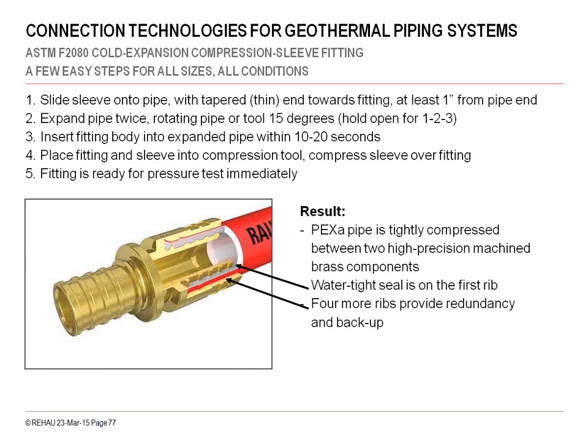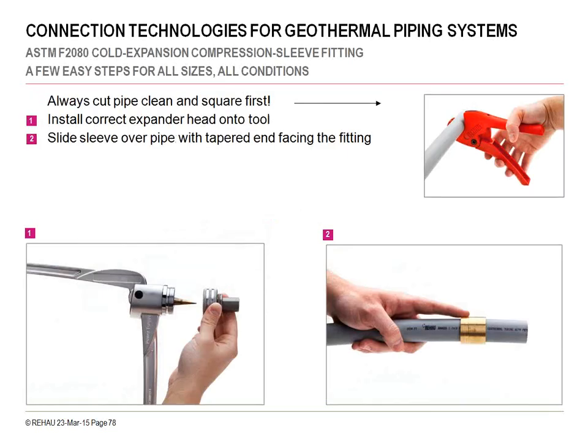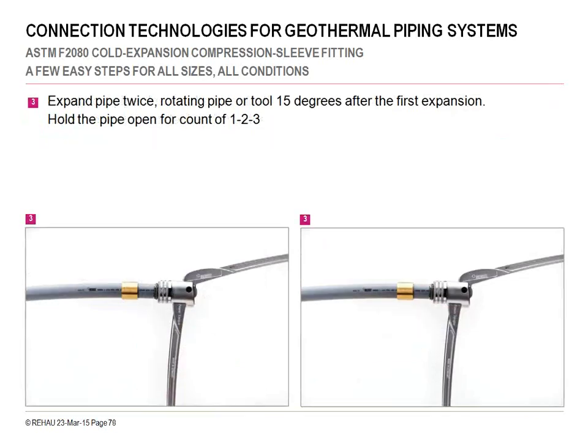If you remember the tensile strength test I was showing you, we get about 4 times the length of the piping material. We're putting about 800 pounds of force on when we're stretching that pipe out. And again, it's the pipe that gets real thin and snaps and fails, and that's what we want to see. It's not at the joint. Going through the illustration of that joining method, we want a nice clean cut of the end of the pipe. There's an expander tool that has a head that can be removed for different dimensions. You would put the sleeve on before expanding the pipe. That's in image 2 there. As you can see, the expander head is inserted in the inside diameter of the pipe. What we're doing is compressing that down, and it spreads that head and opens up the inside diameter of the PEX-A pipe.